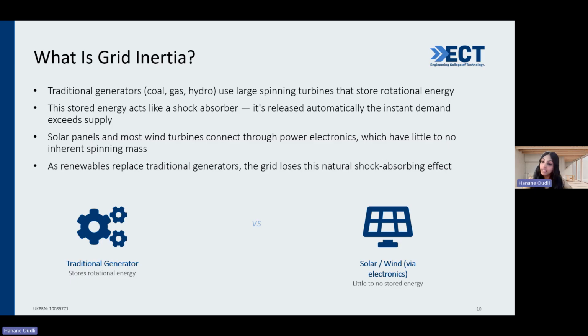Now compare that with solar PV plants. The PV array itself has no rotating mass connected directly to the AC system. Modern wind turbines do have rotational mechanical components, but the power electronic converter can decouple much of that mechanical energy from the grid's instantaneous electromechanical dynamics. That distinction is extremely important.